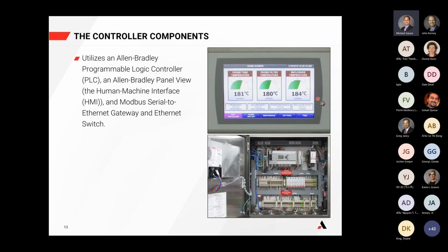But we also need to tie back to the analyzer. And that is done via a gateway and an Ethernet switch tying us back to the 909, the 910, the 919, or the 920 analyzer from AMETEK that would be actually measuring the H2S and the SO2.